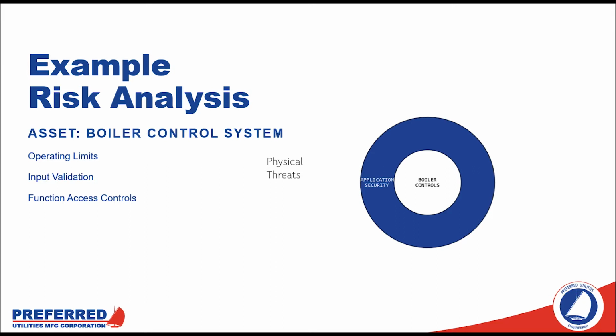Most commonly you can also have functional access controls. Certain features—like modifying how the boiler operates, adjusting combustion curves, or changing parameters on how the boiler responds to a firing rate increase—are only permitted to users who can enter a password asserting they have the correct knowledge and skills to modify those parameters safely.